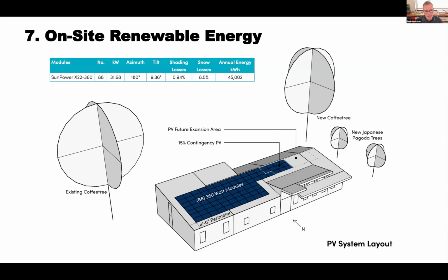We're targeting a system size of 32 kW. Here's the layout on the south-sloping roof. There's a little extra area for PV expansion, and we've also included a 15% PV contingency, knowing that year to year the weather will be different, and there may be differences in occupancy schedule and use, giving a little buffer on the net zero goal. The trees are shown here because there's actually quite a bit of coordination with the landscape architect, making sure we understand the height the trees would grow to and that they wouldn't shade the roof.